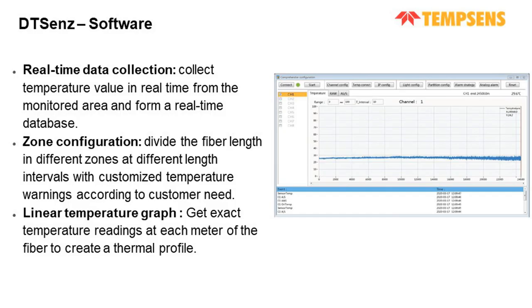Additionally, the DTS system generates a linear temperature profile with spatial resolution as fine as 1 meter or 0.5 meter. This means that the temperature data is available for every meter of fiber, providing a detailed and continuous thermal map of the monitored asset or environment. The resulting thermal profile allows for precise identification of hotspots, thermal gradients, and unusual patterns, which are critical for early fault detection, insulation integrity assessment, and system reliability analysis. Together, these capabilities make DTS an invaluable tool for advanced thermal diagnostics in applications such as high voltage power cables, pipelines, tunnels, and industrial process monitoring, delivering both operational insight and safety assurance.